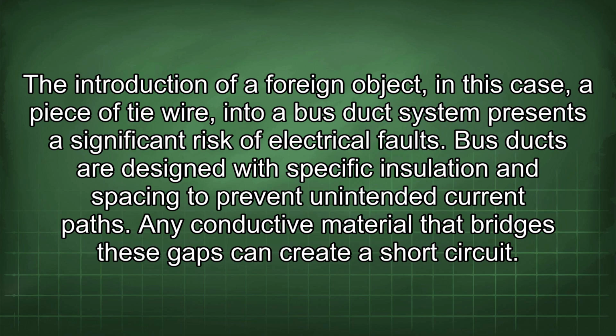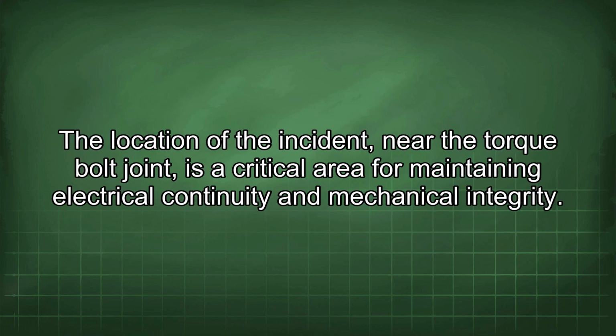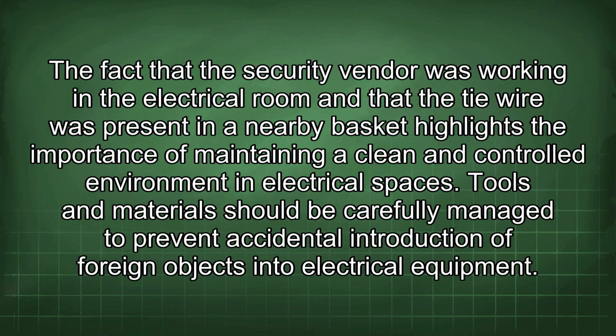Bus ducts are designed with specific insulation and spacing to prevent unintended current paths. Any conductive material that bridges these gaps can create a short circuit. The location of the incident, near the torque bolt joint, is a critical area for maintaining electrical continuity and mechanical integrity. The fact that the security vendor was working in the electrical room and that the tie wire was present in a nearby basket highlights the importance of maintaining a clean and controlled environment in electrical spaces. Tools and materials should be carefully managed to prevent accidental introduction of foreign objects into electrical equipment.